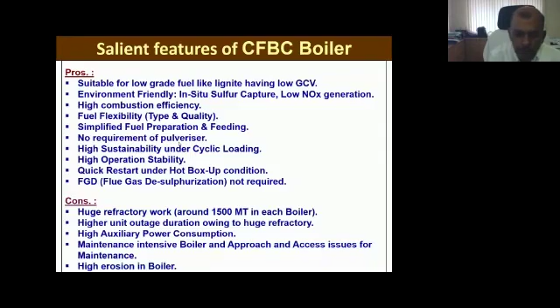The major disadvantage of this technology is higher auxiliary consumption. Instead of 10% for this size of PF boiler, the auxiliary consumption is 12 to 13%. Earlier we were achieving it in the 11.5% range when we had good fuel and lower moisture. Now it is almost 13.25 and 12.5, so a range is there. On account of auxiliary consumption, we are losing 3% of our generation and not able to export it to the grid. So this is our internal consumption.